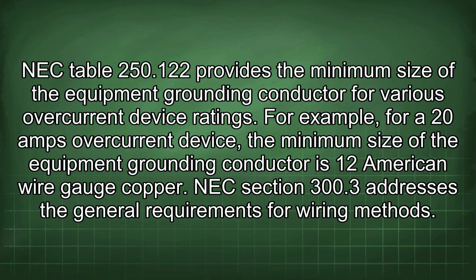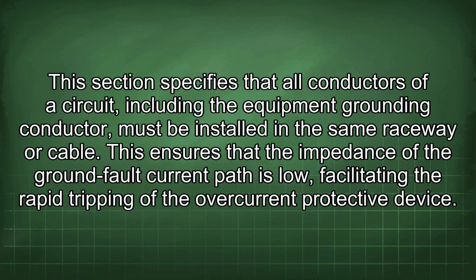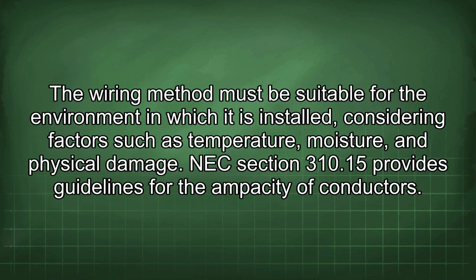gauge copper. NEC Section 300.3 addresses the general requirements for wiring methods. This section specifies that all conductors of a circuit, including the equipment grounding conductor, must be installed in the same raceway or cable. This ensures that the impedance of the ground fault current path is low, facilitating the rapid tripping of the overcurrent protective device.